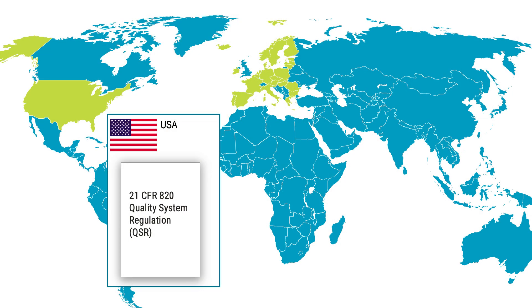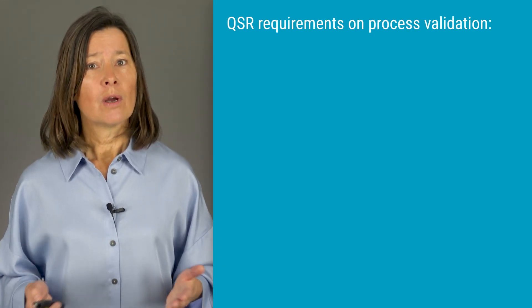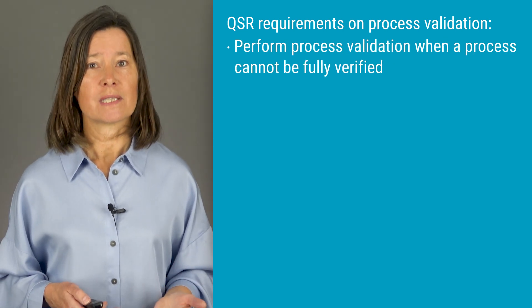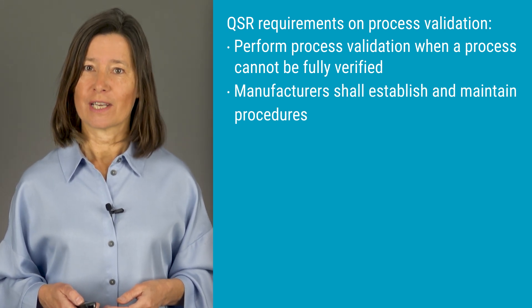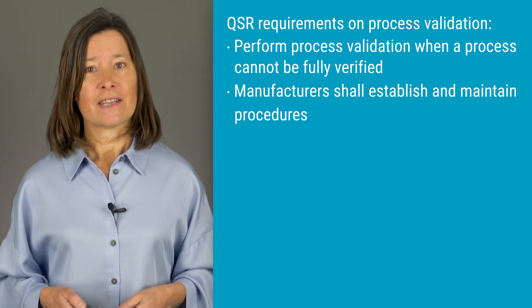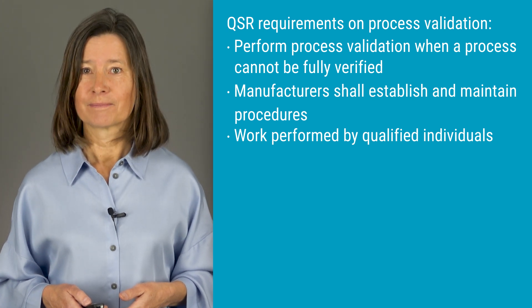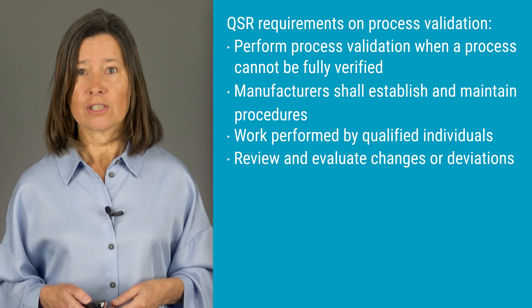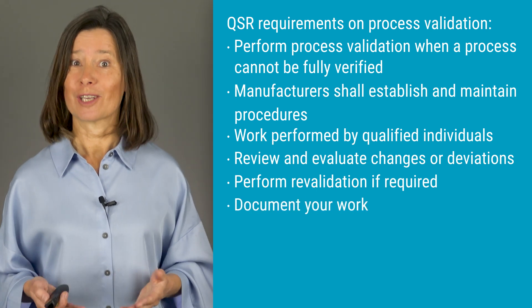For medical devices sold to the US market, process validation is required by a regulation known as 21 CFR Part 820 Quality System Regulation, often referred to as the QSR. Section 820.75 of the QSR tells us when we must perform process validation, which is when a process cannot be fully verified by subsequent inspection and testing. It also requires manufacturers to establish and maintain procedures for monitoring and controlling process parameters for validated processes, and that personnel involved in validated manufacturing processes are qualified. It also requires review and evaluation of changes or deviations to processes and revalidation if required, and of course documentation.